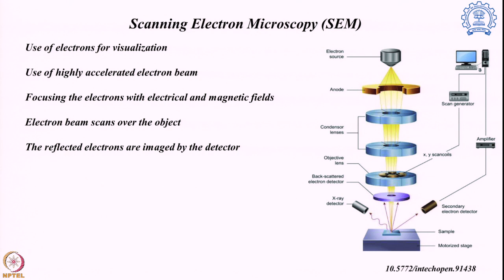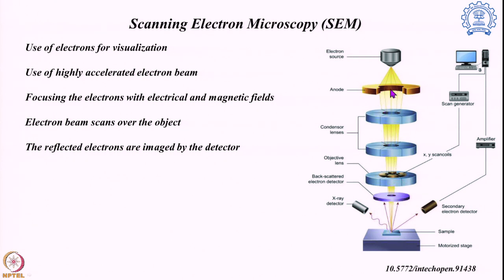One complementary electron microscopy technique after TEM is scanning electron microscopy, or SEM. Here we also use a similar electron source with accelerated, fast-moving, high-energetic electrons. Again we use electromagnetic lenses to focus the sample, where the electrical and magnetic field through these lenses converts a widely spreading electron beam into a very focused electron beam, which is then directed onto the sample.